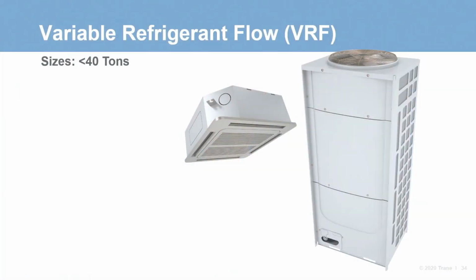Next, we'll look at another split system, variable refrigerant flow, or VRF. These systems are probably the most popular heat pump system on the market today. Their capacity per unit is typically less than 40 tons, but they can be linked together to form larger systems. Over the last 5 years, we've seen VRF applications grow in number. Some of the more popular are schools, offices, and any kind of mixed-use space.